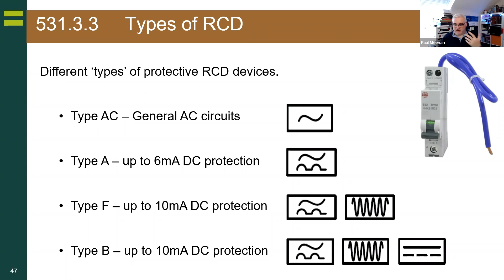Okay. Now, only if you've got really bad luck will it completely make it not work, and that takes quite a large amount of DC. In the domestic home, not so much. So that needs to be considered when you're selecting an RCD. There's a great European standard that's got some nice visuals that talk about how you configure your RCDs. Please note there's no AC type on these. And anything that's Type B, you obviously want to configure it so it's above Type A. That way you don't have any DC leakage overwhelming your Type A devices.